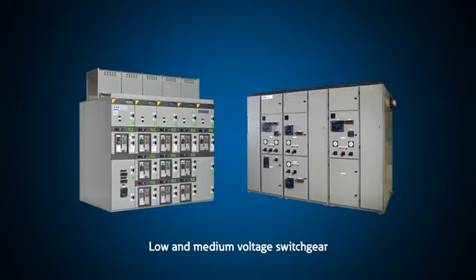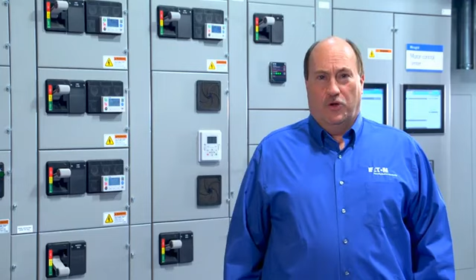This MCC is the common bus for accumulating all of the microgrid sources and loads. In a much larger system, this would typically be low voltage or medium voltage switchgear. Recall that a primary driver for microgrid is resiliency. That is the ability to continue powering loads in the event of a utility disruption. When the microgrid is operating independent of external sources, we say the microgrid is islanded.